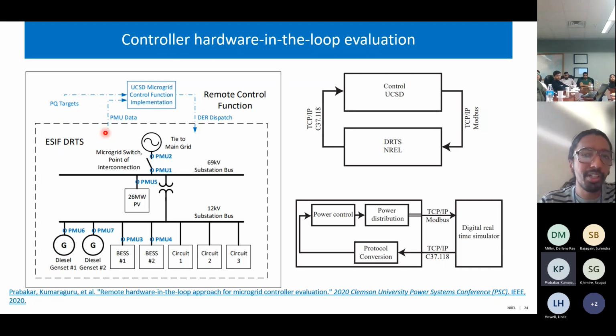So we sent PMU data from these PMU locations to UCSD, and UCSD made decisions based on that, running their optimization and sending DER dispatch back to NREL's ESIF. We ran this for different load profiles and different PV profiles to understand whether this microgrid, or the controller, can handle it.